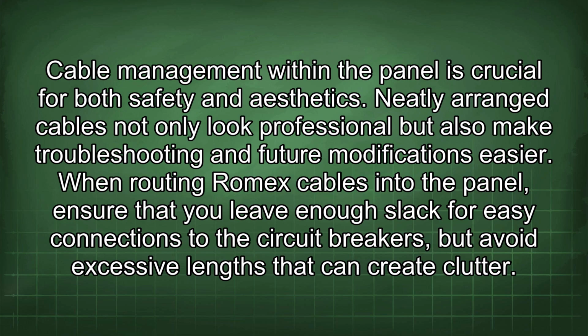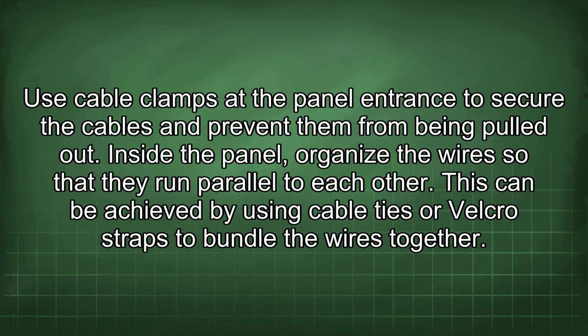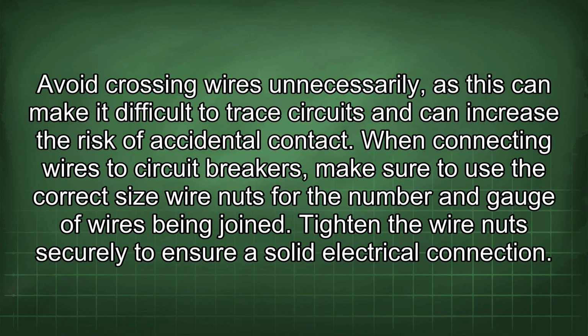When routing Romex cables into the panel, ensure that you leave enough slack for easy connections to the circuit breakers, but avoid excessive lengths that can create clutter. Use cable clamps at the panel entrance to secure the cables and prevent them from being pulled out. Inside the panel, organize the wires so that they run parallel to each other. This can be achieved by using cable ties or Velcro straps to bundle the wires together. Avoid crossing wires unnecessarily, as this can make it difficult to trace circuits and can increase the risk of accidental contact.